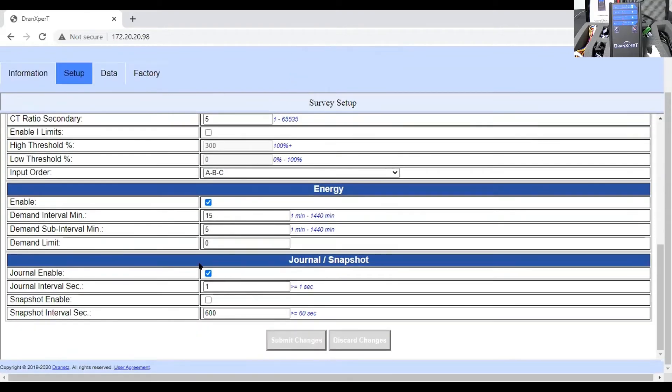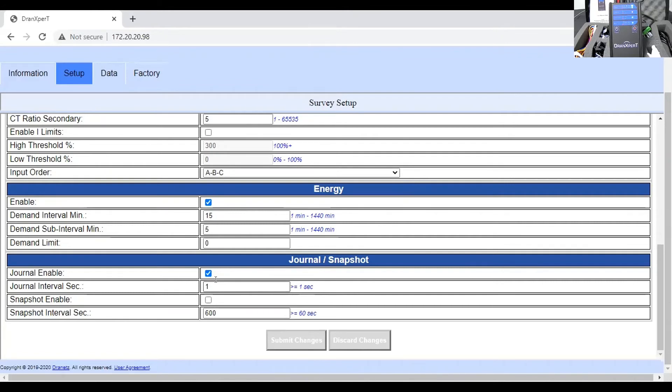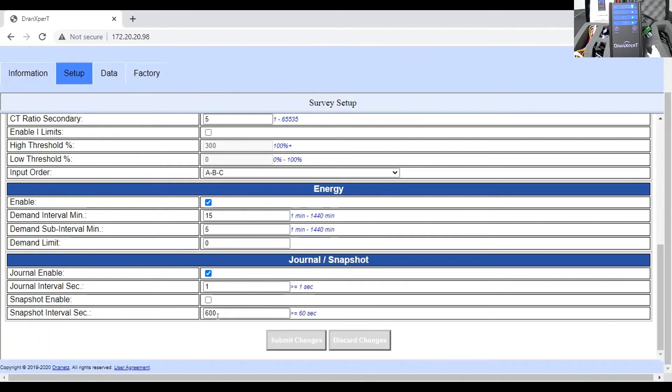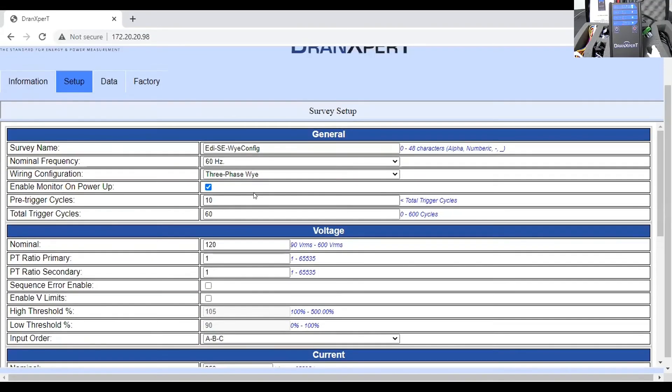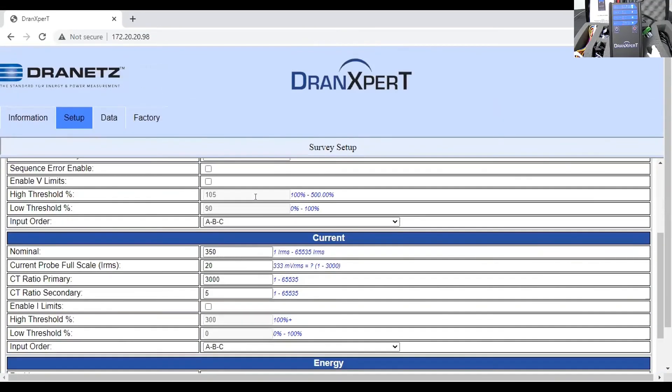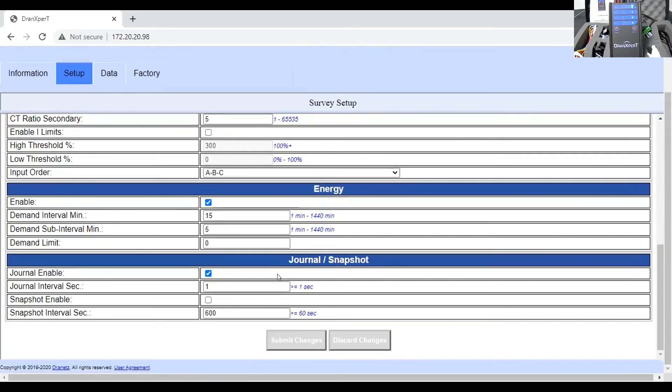Incidentally, the instrument has a set of LEDs, and one of those LEDs refers to demand limit. Just simply walking up to the instrument and seeing if the LED is red or green would indicate if you're within your demand limits or not. So that's a neat little feature that the instrument has. And then of course, we have data logging. In the data logging world, they're called journals. And so you have a journal interval. You can see in this instance here, we're using a one-second interval in which it goes out and collect journal data. Some people refer to it as data logs. It's a data set in which an instrument goes out and provides your basic meter readings, your harmonics, etc. There's even more of what I would call more of an advanced option where maybe you want to, in addition to journals, you want to take snapshots of waveforms. And it's a matter of enabling it and then choosing an appropriate interval. And the instrument will go out and take a waveform snapshot at the user-defined interval. Once you've configured this page for a given application, then it's just submitting the changes. And the changes are uploaded to the instrument.